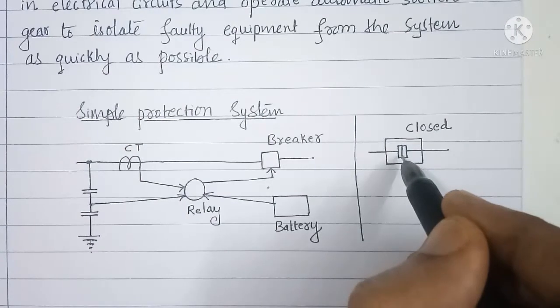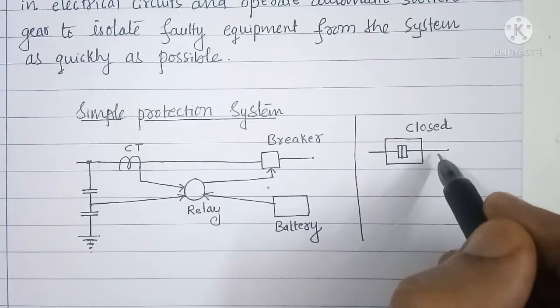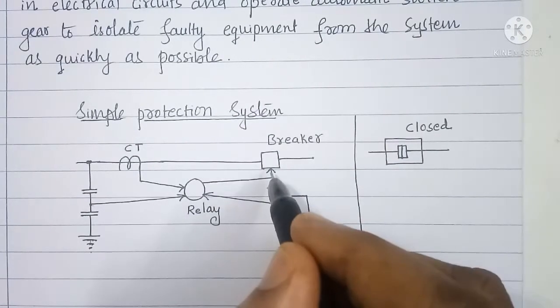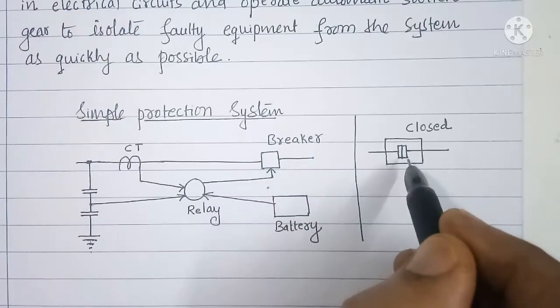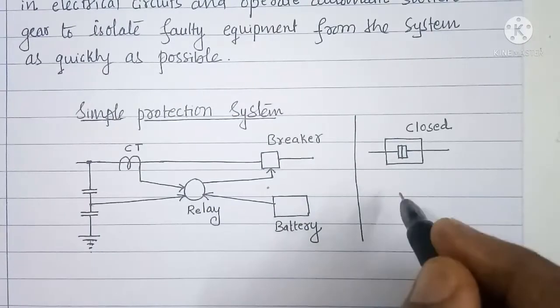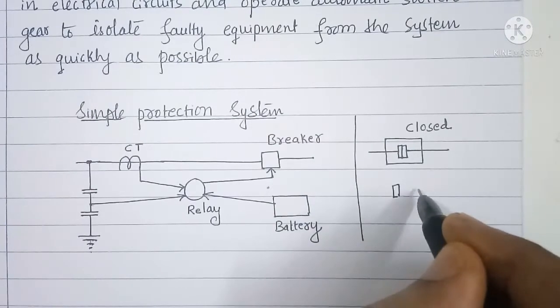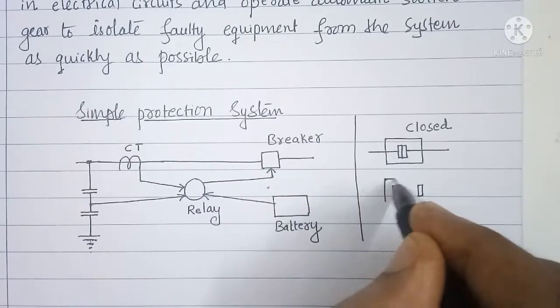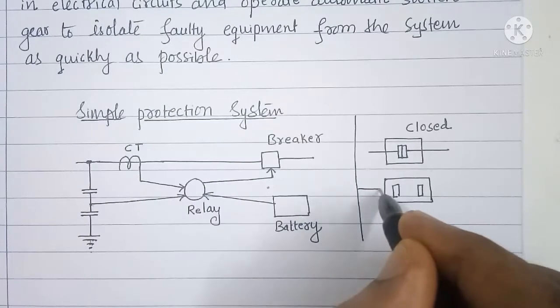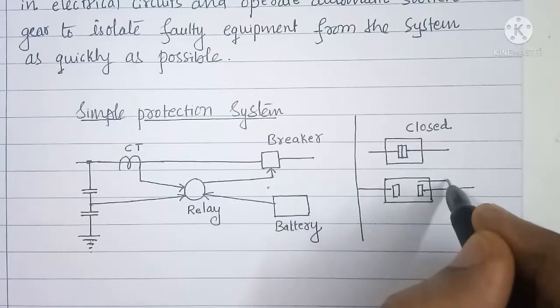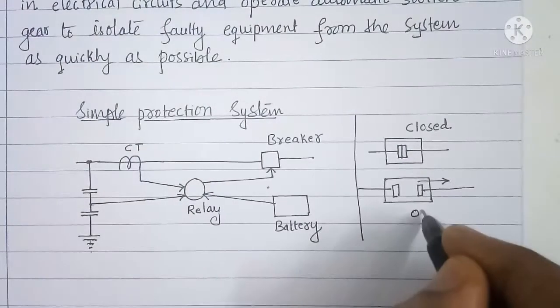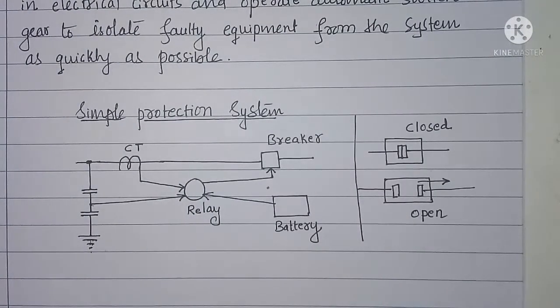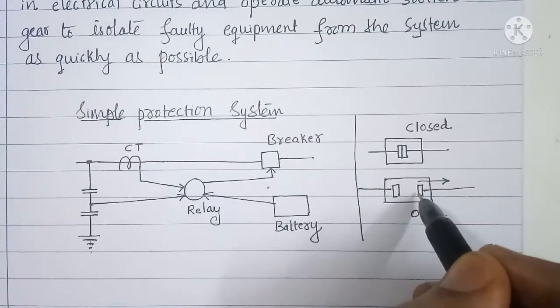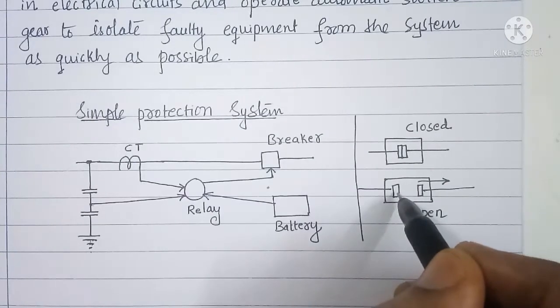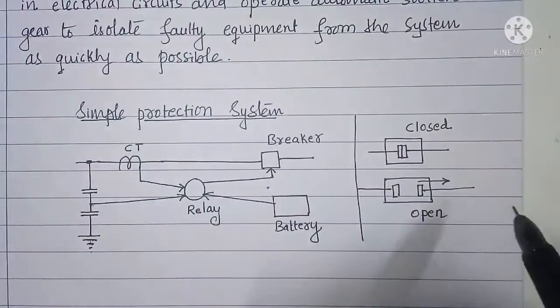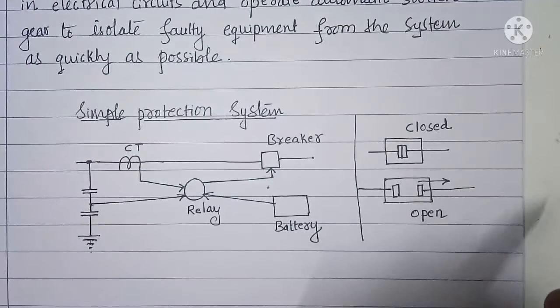Out of these two contacts, one contact will be fixed and another one will be movable. When a fault occurs and the trip signal is issued to the circuit breaker, the movable contact moves away from the fixed contact. That may be shown like this. Say this contact has moved away. Now the circuit breaker is open. So when the circuit breaker operates, the contact surfaces get separated and the current flow ceases. That is, faulty equipment is isolated from the healthy part of the power system.